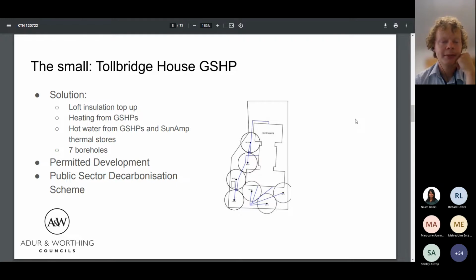It saw 7 boreholes drilled into the ground in the car park to a depth of up to 180 metres. For consistency with the project's sister site that I'll introduce shortly, we've installed those phase change batteries, the Sunamps, that Richard mentioned earlier. That means there's now no stored hot water on site, significantly reducing the Legionella risk our residents may face.